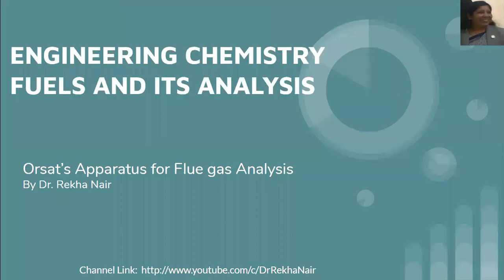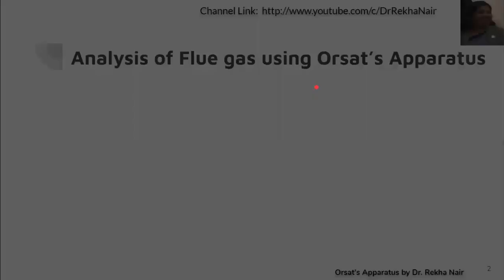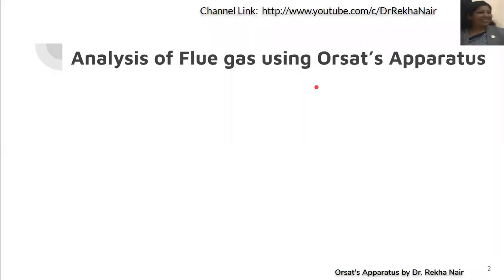Hello everyone. Today we are going to discuss about the Orsat apparatus. The Orsat apparatus is used for analysis of flue gas. Flue gas means it is the waste gases after the combustion process that are coming out from the chimney.